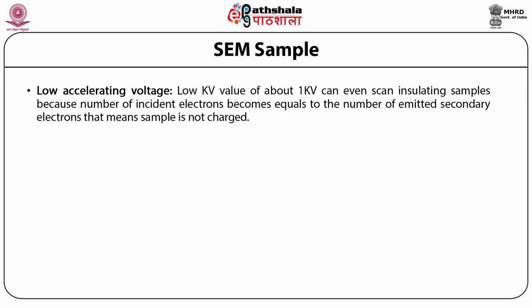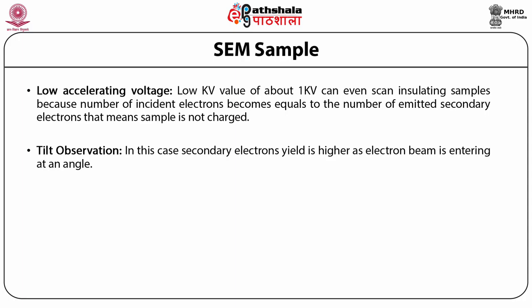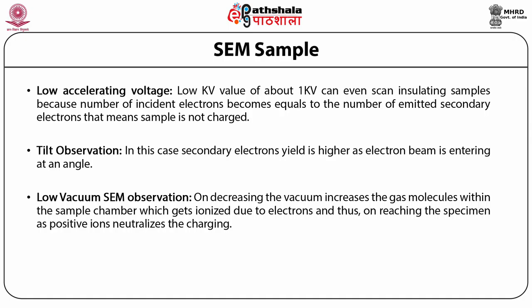Next is tilt observation. In this case, secondary electron yield is higher as the electron beam is entering at an angle. Next is low vacuum SEM observation. On decreasing the vacuum, it increases the gas molecules within the sample chamber, which get ionized due to electrons. Thus, on reaching the specimen as positive ions, they neutralize the charging.